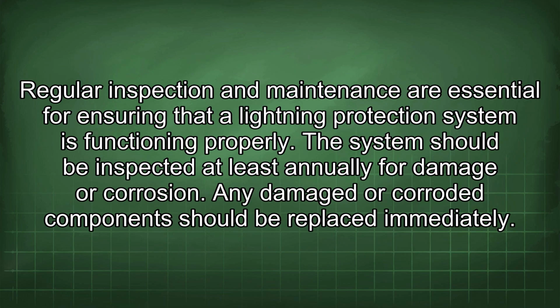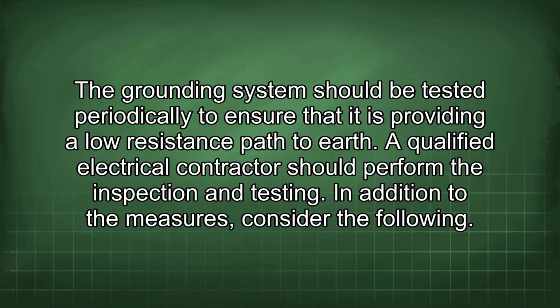Regular inspection and maintenance are essential for ensuring that a lightning protection system is functioning properly. The system should be inspected at least annually for damage or corrosion. Any damaged or corroded components should be replaced immediately. The grounding system should be tested periodically to ensure that it is providing a low resistance path to earth. A qualified electrical contractor should perform the inspection and testing.